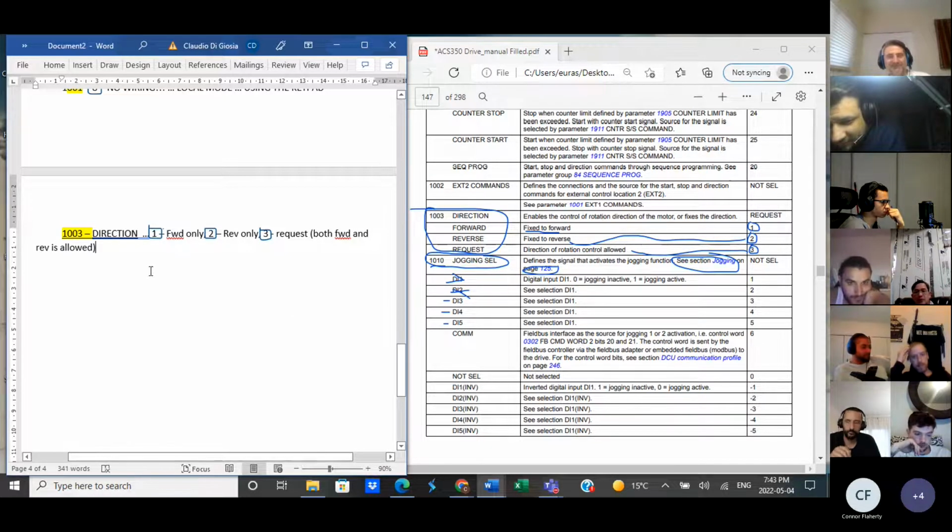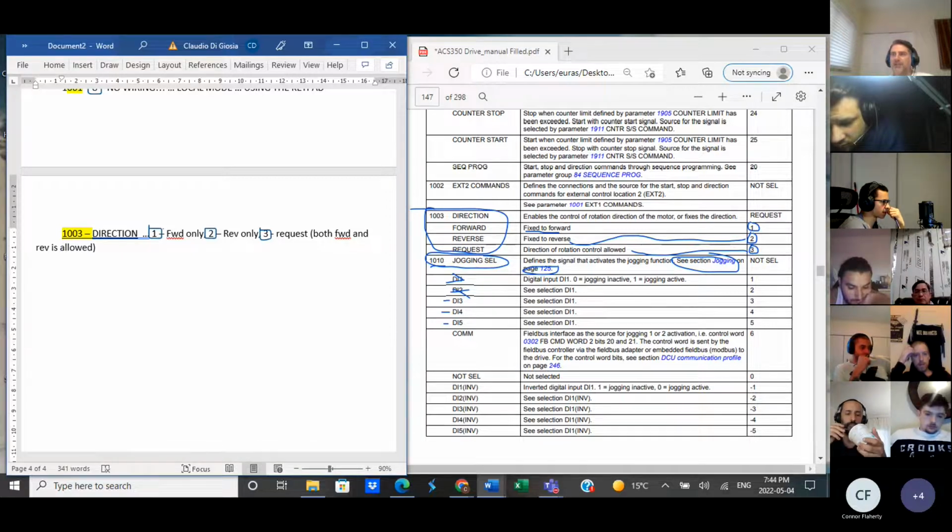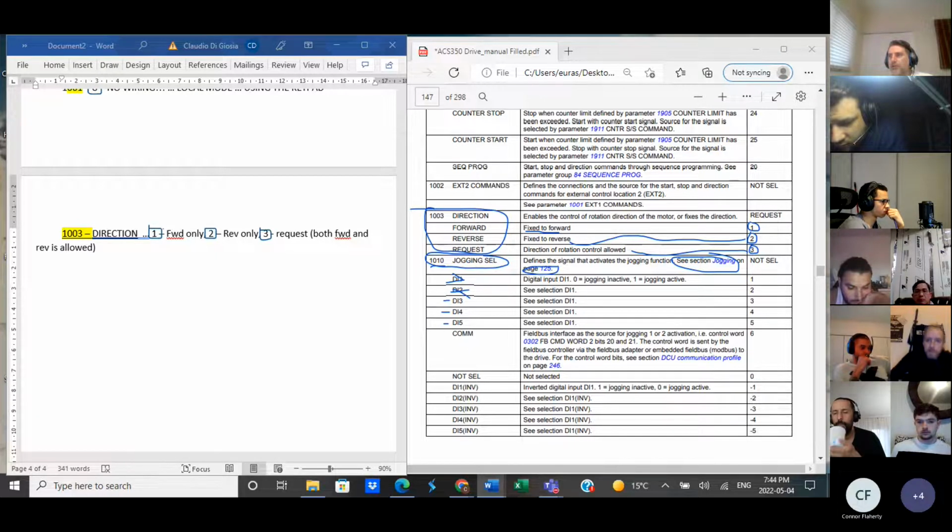You have? Okay, so basically, the last thing I did in that video was change direction. So in order for me to be able to change direction, 1003 had to have been programmed to 3. Otherwise, it would not have changed direction. Okay. All right. So the next one is 1010 jog. So 1010 jog or jog select is right here.